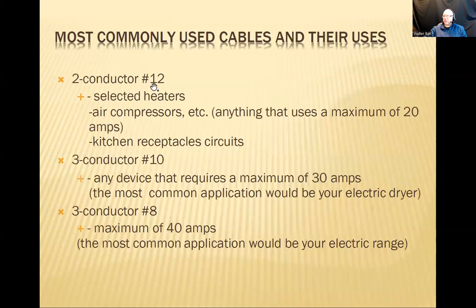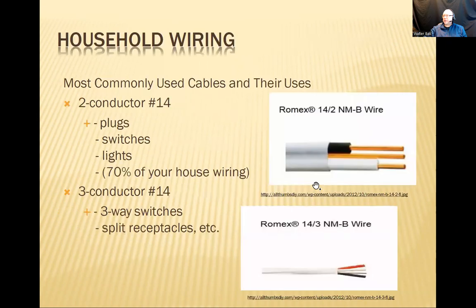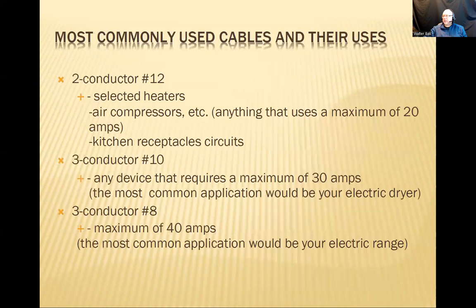Now look at this. Here's 12 gauge, which is a thicker wire, which is supposed to carry more current. So here's a 12-2. It will be used for heaters. Heaters take more space, more current. Air compressors, anything that uses a maximum of 20 amps. Kitchen receptacle circuits as well. 3 conductor, okay, so 10-3, any device that requires a maximum of 30 amps. And an amp is a unit of current. So you see here, 14 is rated for 15 amps. Then gauge 12 is a thicker wire. It's rated for 20 amps. Then we go down with the gauge, the wire becomes thicker, and you go to 30 amps. And then we go even thicker wire, 8 gauge, with a maximum of 40 amps.